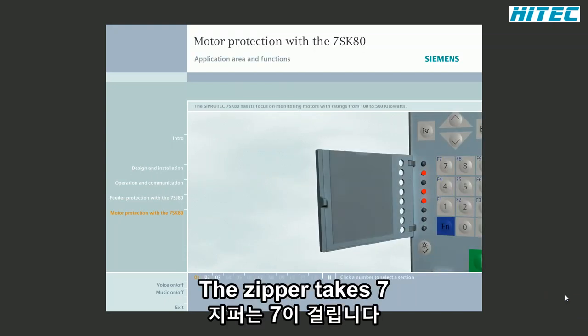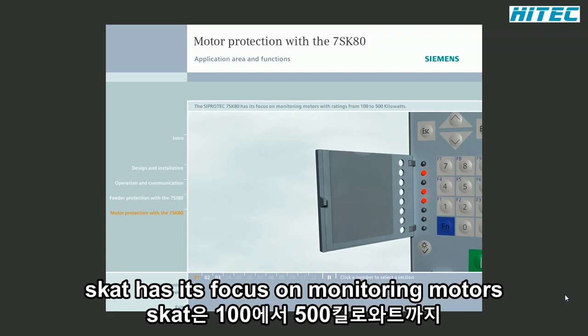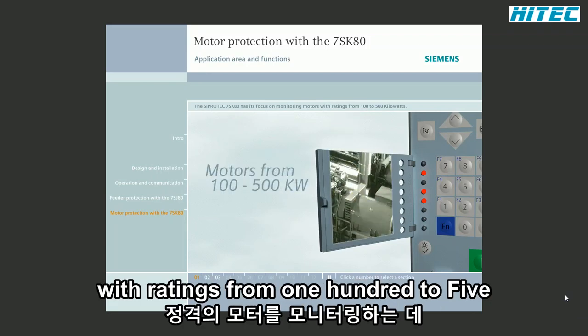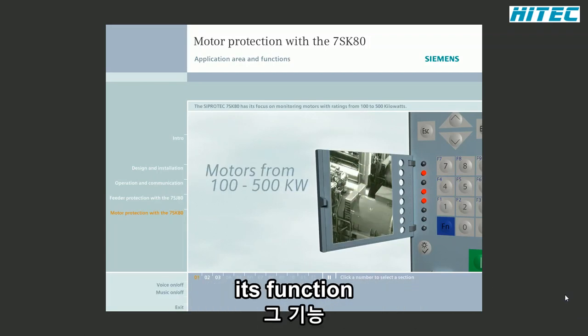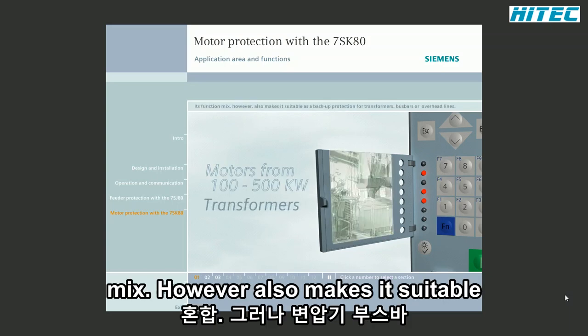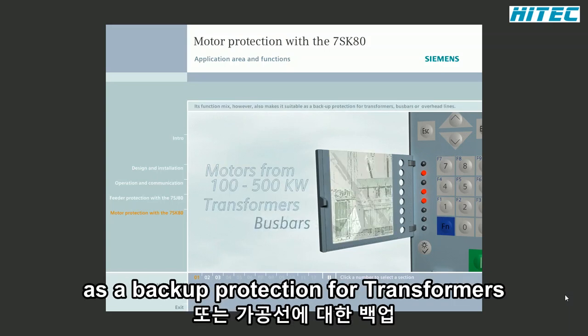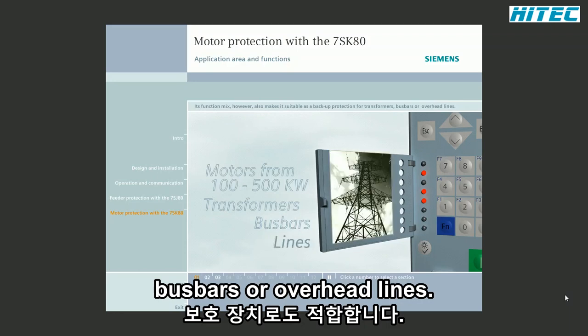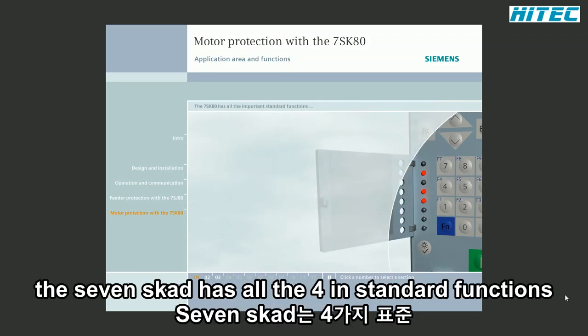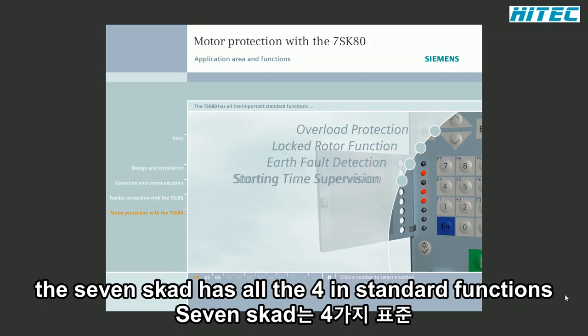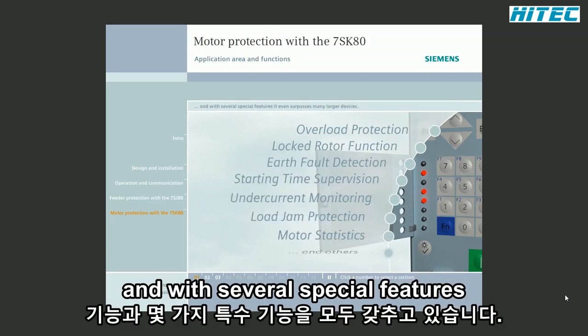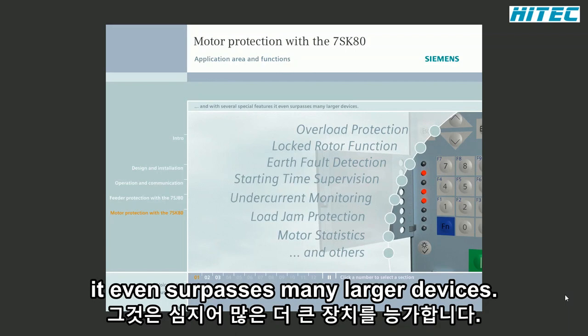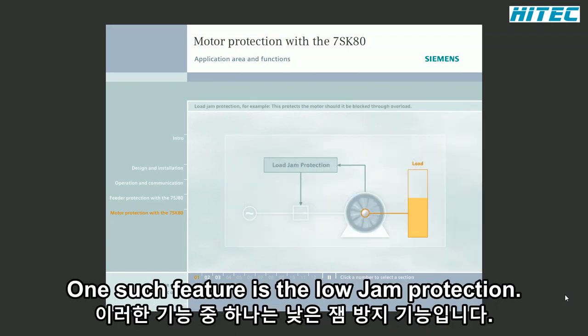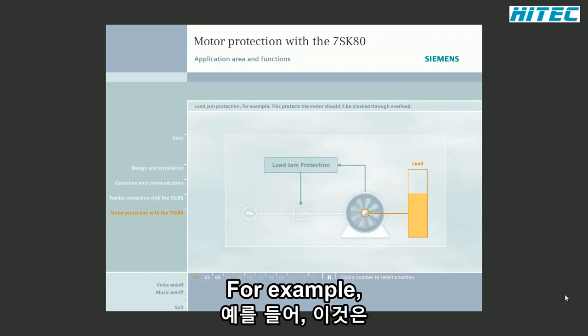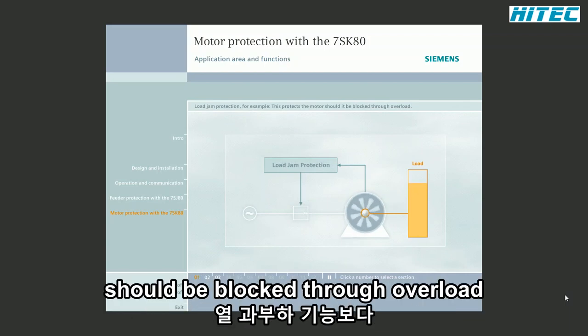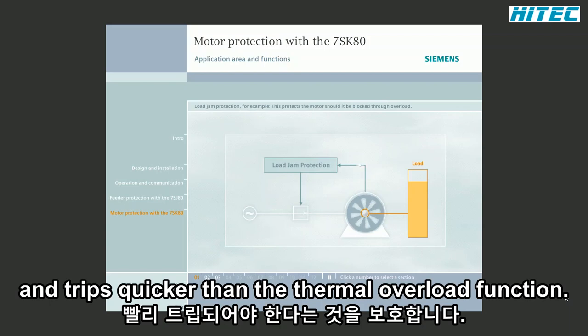The SIPROTEC 7SK80 has its focus on monitoring motors with ratings from 100 to 500 kilowatts. Its function mix, however, also makes it suitable as a backup protection for transformers, bus bars, or overhead lines. The 7SK80 has all the important standard functions, and with several special features, it even surpasses many larger devices. One such feature is the load jam protection, for example. This protects the motor should it be blocked through overload and trips quicker than the thermal overload function.